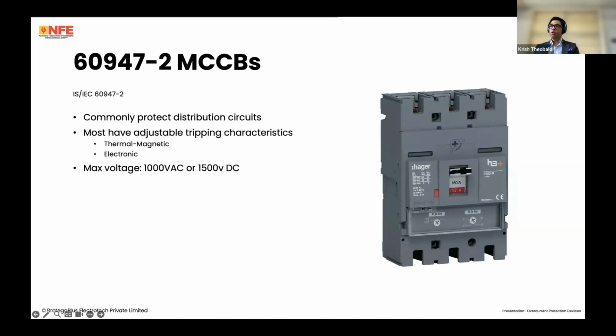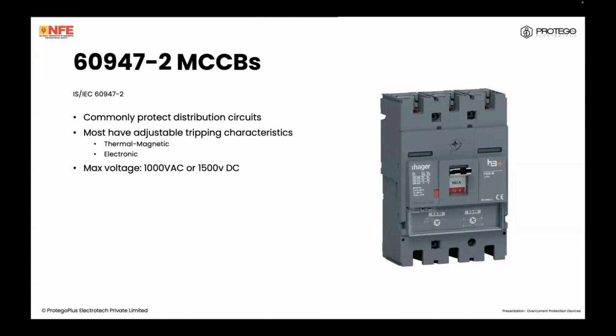These commonly protect distribution circuits, so they would protect the circuit that's supplying a distribution board, a sub-distribution board from a main distribution board. These commonly have adjustable tripping characteristics, so you can see you can set the current, thermal, and magnetic tripping here. I'll show you the different settings available ahead. There are two basic types of MCCBs that are available under the adjustable.